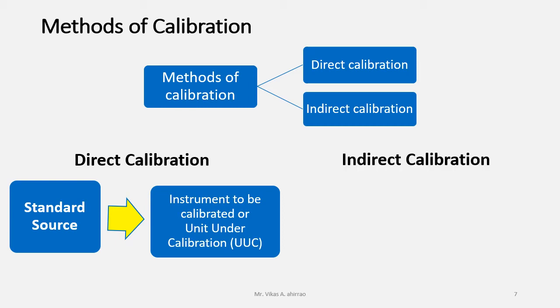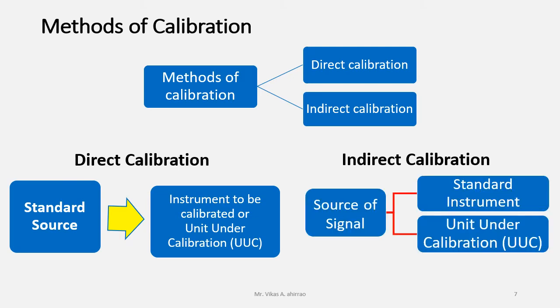The second method is indirect calibration. In this one, there will be a source of signal which is not a standard source. So we will use in this one another standard instrument along with the unit under calibration, that is UUC. When we give the input from the source of signal, the standard instrument having higher accuracy and precision will be compared with the measurement done by the unit under calibration. So these two measurements will be compared, and in this way the calibration will be carried out.